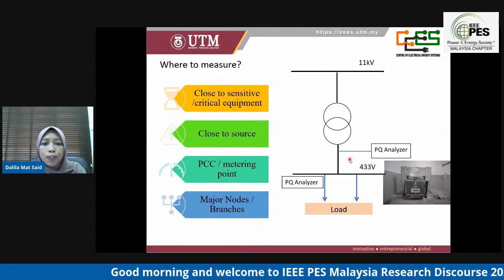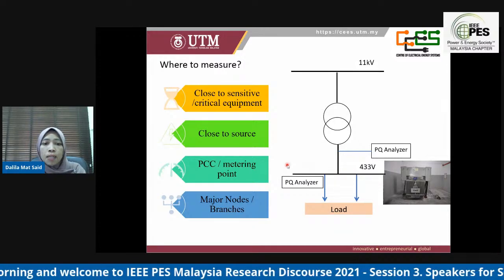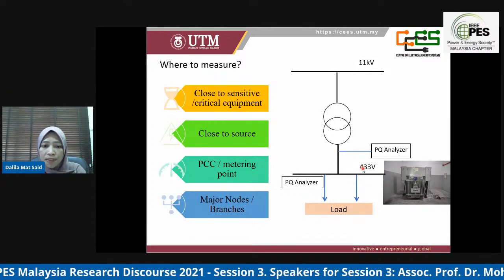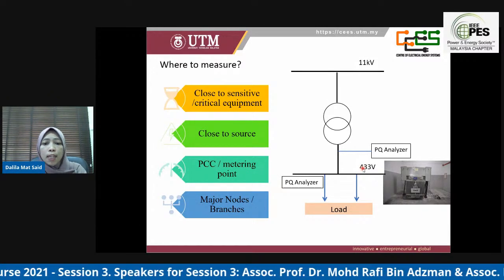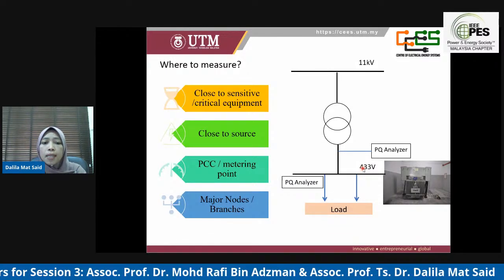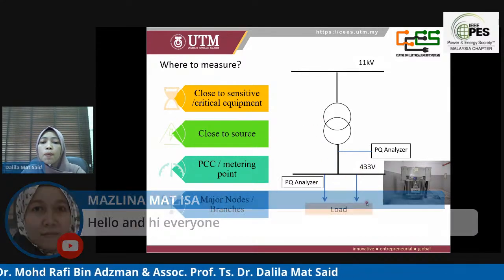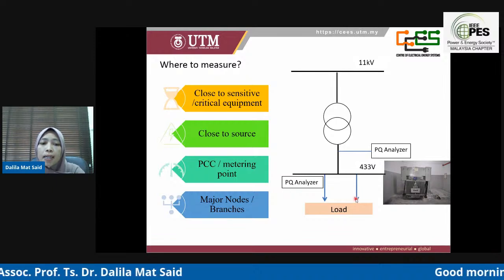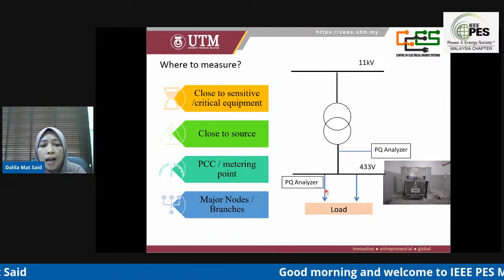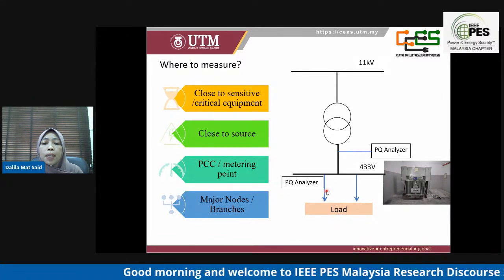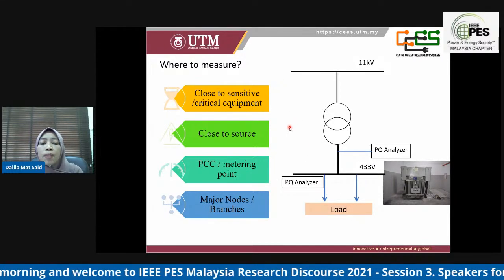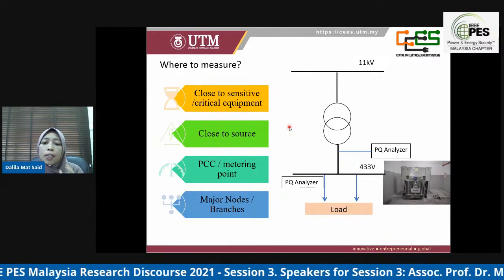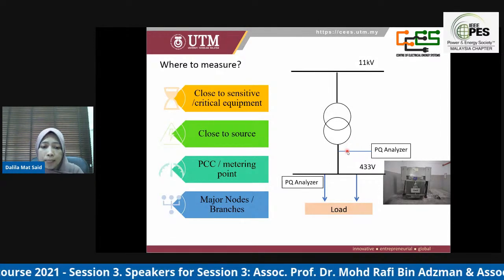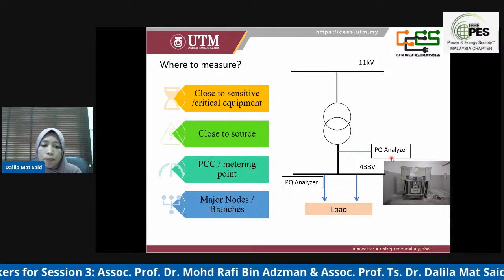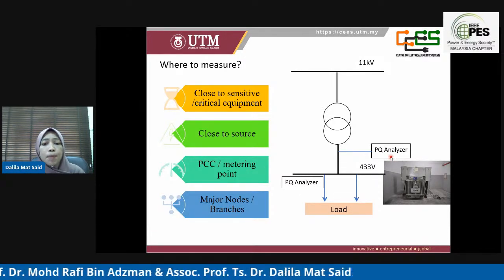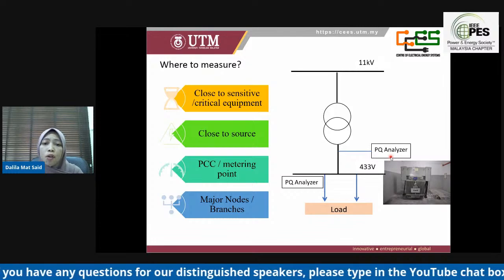Here is the suggestion of where we want to measure. Based on the problem reported, another important aspect of monitor location when characterizing a specific power quality problem is to locate the monitor as close as possible to the equipment affected by the power quality variation. If there is suspected equipment, we need to install the PQ recorder close to that sensitive equipment. If the problem occurs at the entire facility, the suitable location is close to the source or at the PCC or at the secondary side of the transformer. If we suspect all equipment connected to the branch exhibits the problem, we can put it at a major node or branches.